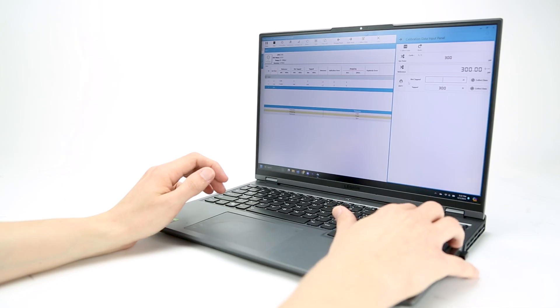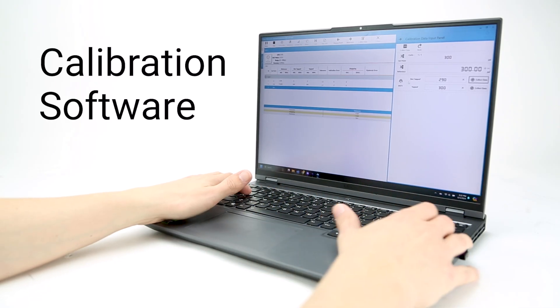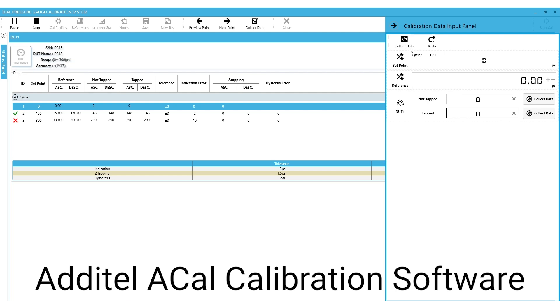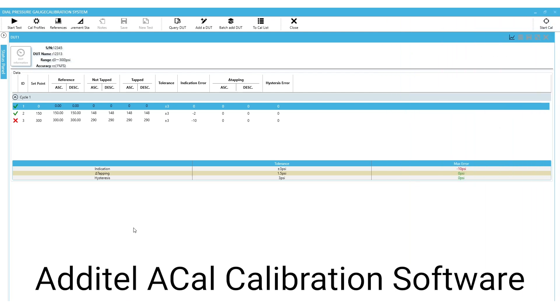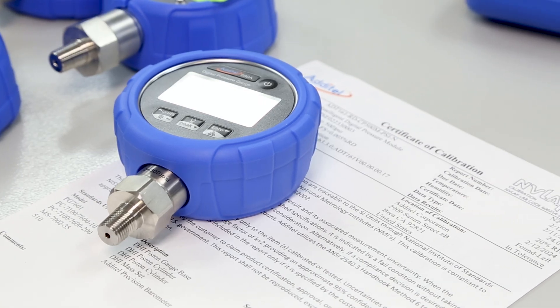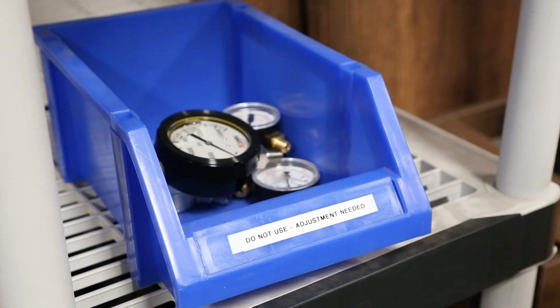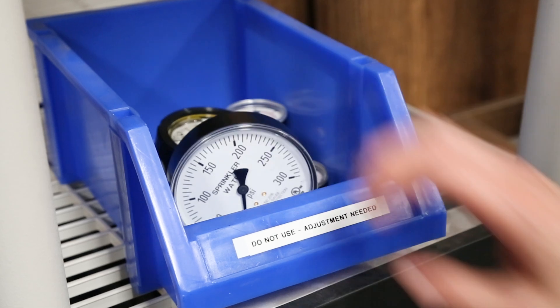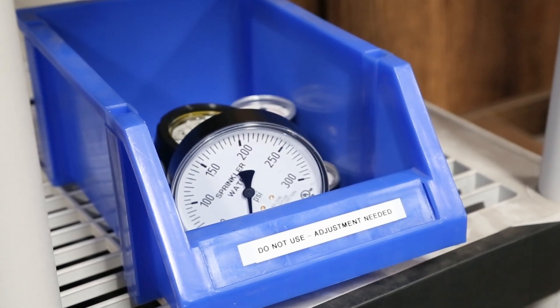That's it! The data you recorded can now be entered into a calibration software to generate a certificate. The software will calculate the error between the DUT and the reference across the pressure range to determine whether the gauge passed or failed calibration. If the gauge is found within tolerance, no action is needed. If the gauge is out of tolerance, it must be either replaced or adjusted according to the manufacturer's instructions.